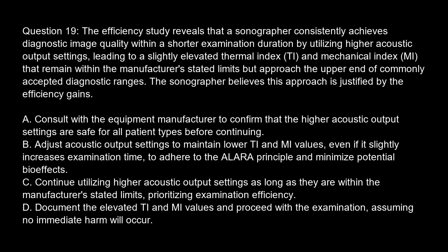Question 19. The efficiency study reveals that a sonographer consistently achieves diagnostic image quality within a shorter examination duration by utilizing higher acoustic output settings, leading to a slightly elevated thermal index, TI, and mechanical index, MI, that remain within the manufacturer's stated limits, but approach the upper end of commonly accepted diagnostic ranges. The sonographer believes this approach is justified by the efficiency gains.